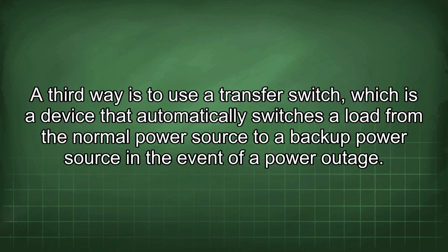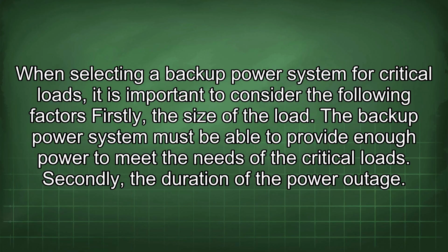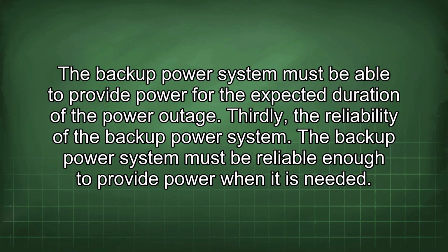A third way is to use a transfer switch, which is a device that automatically switches a load from the normal power source to a backup power source in the event of a power outage. When selecting a backup power system for critical loads, it is important to consider the following factors. Firstly, the size of the load. The backup power system must be able to provide enough power to meet the needs of the critical loads. Secondly, the duration of the power outage. The backup power system must be able to provide power for the expected duration of the power outage.